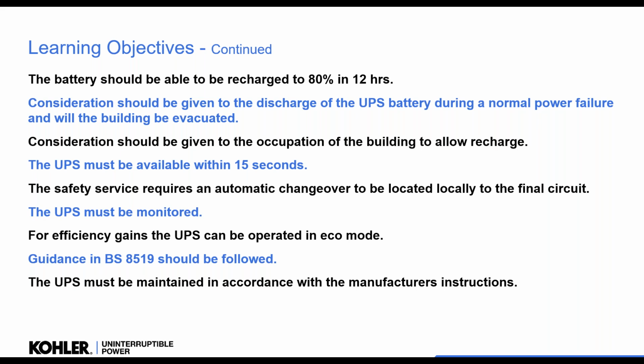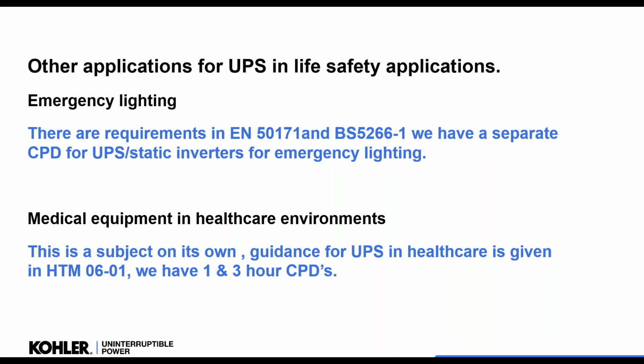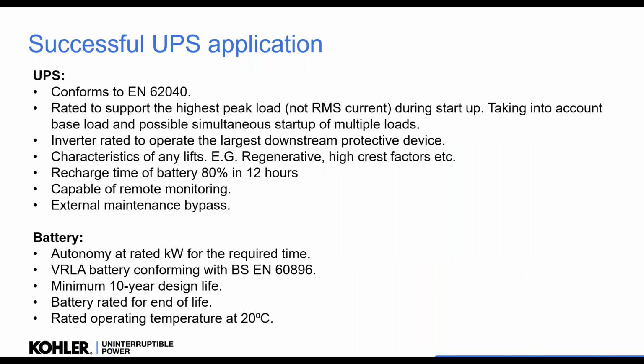And then we have the guidance in 8519, very important to read that. Okay, and then once it's installed, maintain it in accordance with the manufacturer's instructions. It's a legal requirement. It must be done by an OEM, and make sure that that system is operational. Again, we talk to people writing the regulations, and we help, and there seems to be a general thing that if you have a life safety system, it doesn't need to be tested. It does. Okay, it's very, very important. Okay, so there are other applications, obviously, emergency lighting and medical equipment. There are different regulations around those. Okay, obviously here on the healthcare, we know about the HTM and how to do it, but we do have other CPDs around those specific subjects. Okay, so we're looking for a successful application.